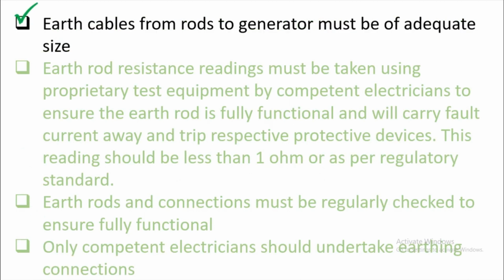Earth cables from rods to generators must be of adequate size. So we need to make sure that the earth cable from the rods to the generator is appropriate in size, because if it is small, it will not withstand the current, and it will immediately cut during the current leakage.